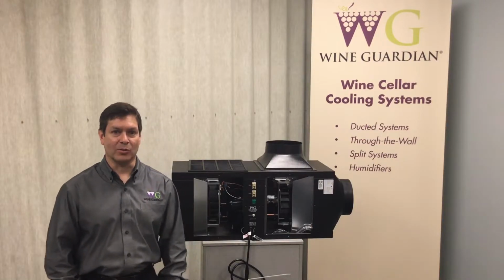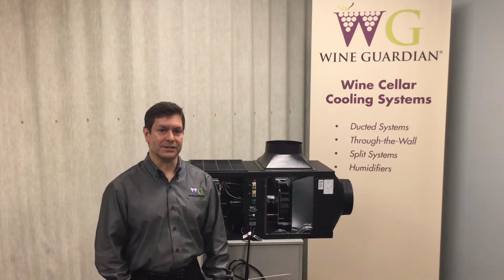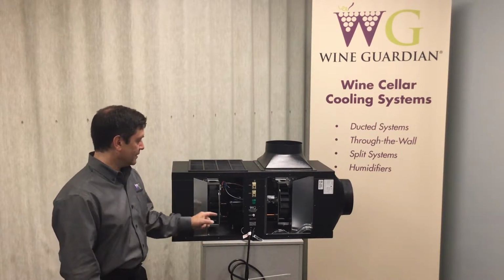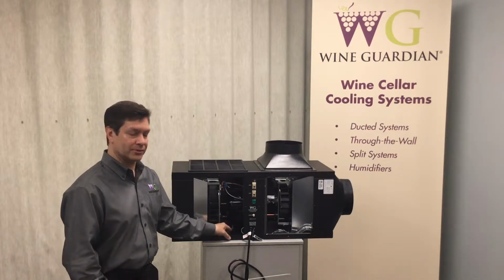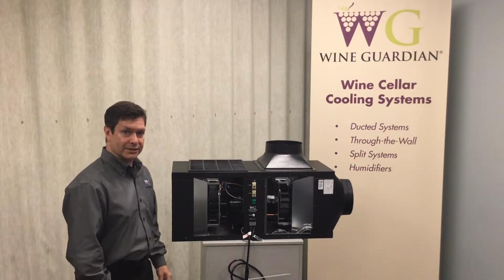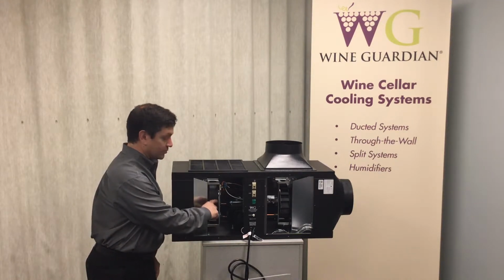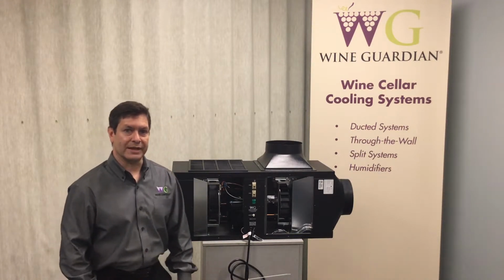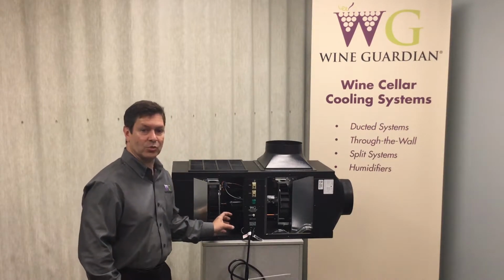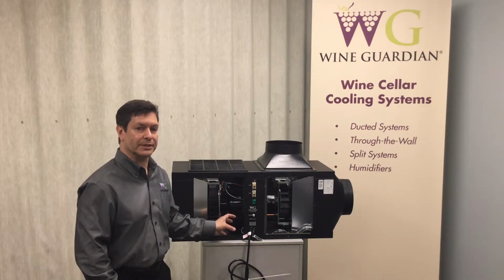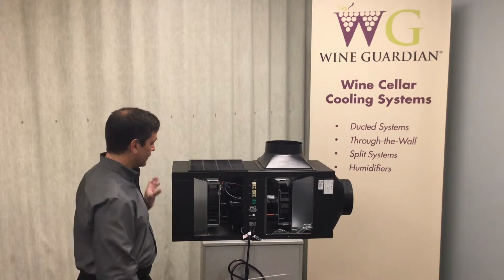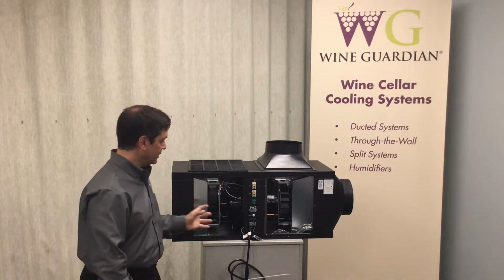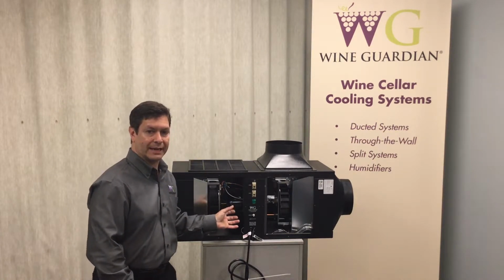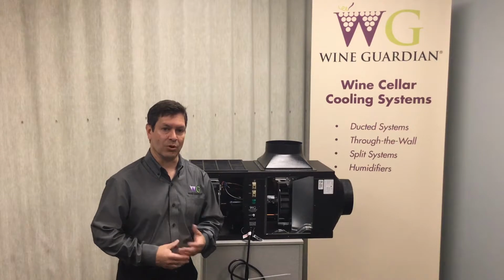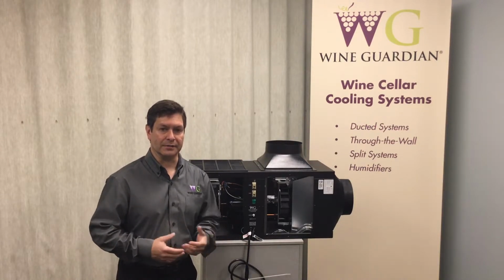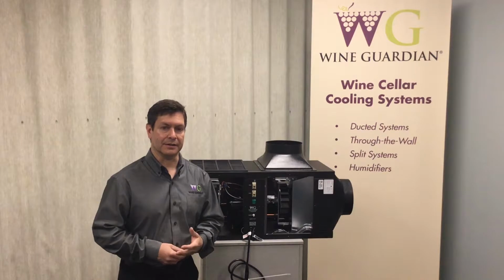The low ambient option as part of the Wine Guardian cooling systems consists of a crankcase heater that typically gets mounted underneath the compressor, and also a fan cycling switch that controls the condenser fan operation. The crankcase heater keeps the compressor warm in very cold environments. When we're bringing in air from outdoors or a cold area, we want to keep that compressor at a very warm temperature to keep the oils fluid so they continue to lubricate the compressor.